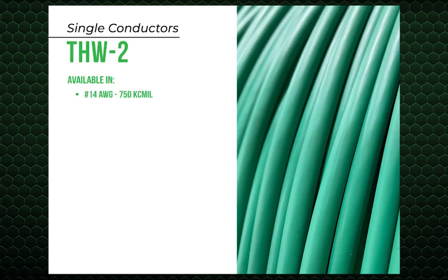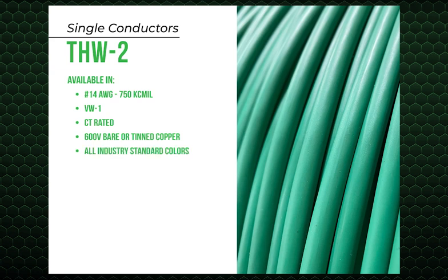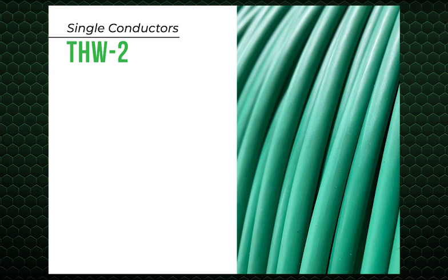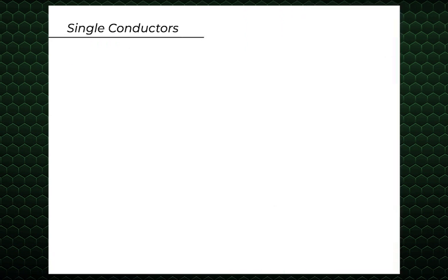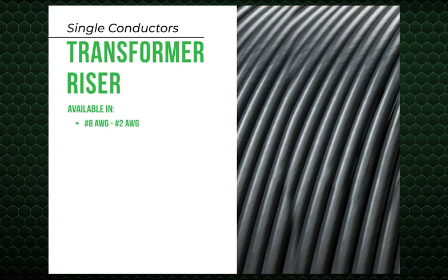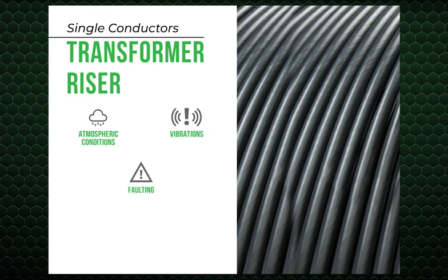THW-2 is available in 14 gauge through 750 kcmil, VW1, CT rated, 600 volt bare or tinned copper in all industry standard colors. THW is used in commercial applications, roadway lighting, and grounding. Transformer riser wire is available in 8 gauge through 2 gauge, solid or stranded copper. This utility product is used as connector wire from the transformer to the power lines. Transformer riser eliminates faults from atmospheric conditions, vibrations, and faulting caused by objects crossing leads. It is used in riser applications at high voltages.